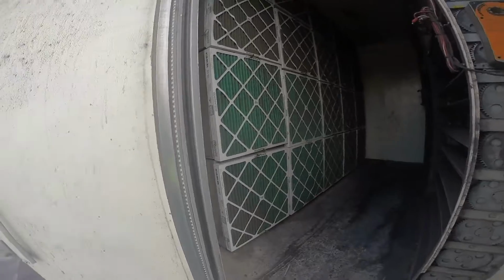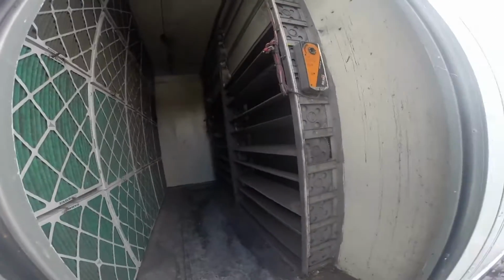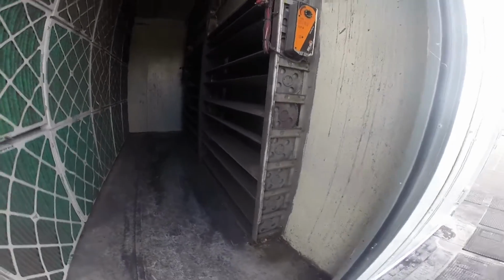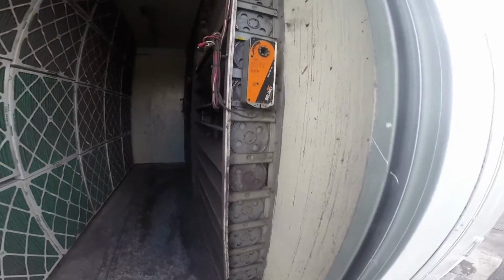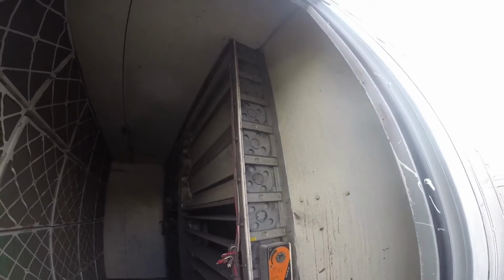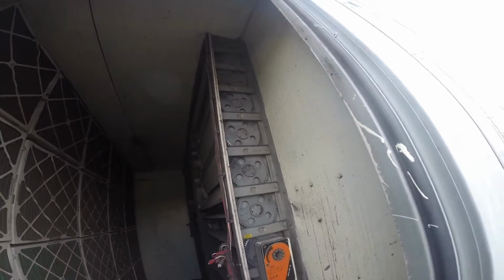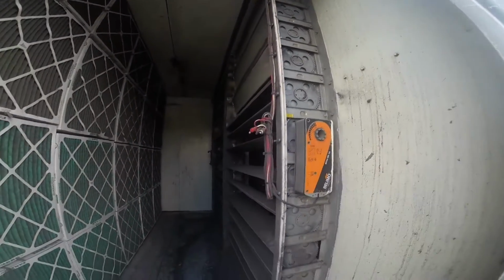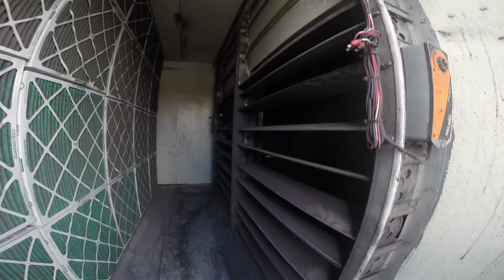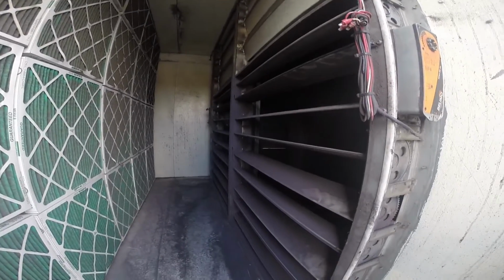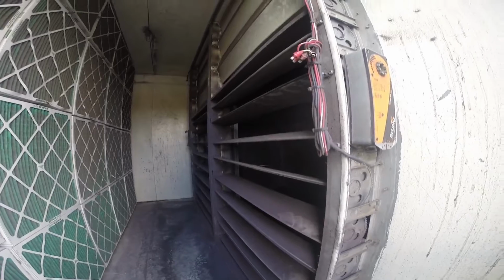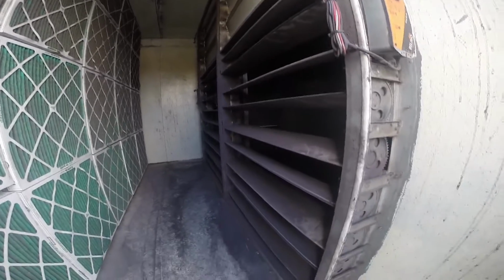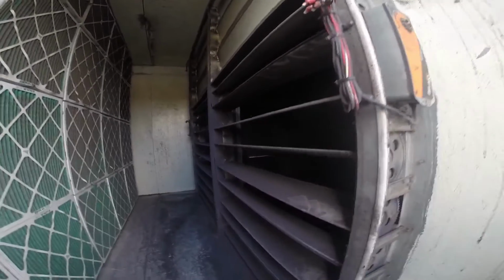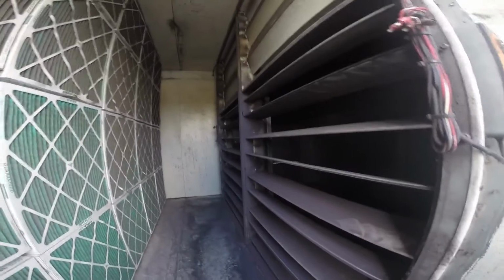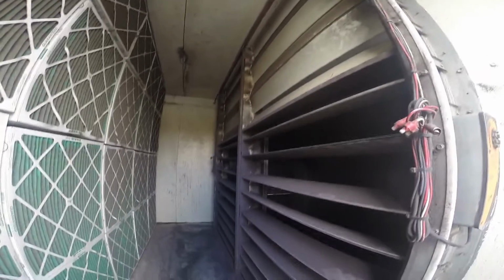Alright, this here would be the filter section and the dampers area. You can tell the damper gears are worn pretty good. The holes where the damper gears go through are worn out, so I don't think we can put any kind of bushing or anything in there. Some of the dampers are missing some of their seals. I'd recommend just putting a whole new damper section in.